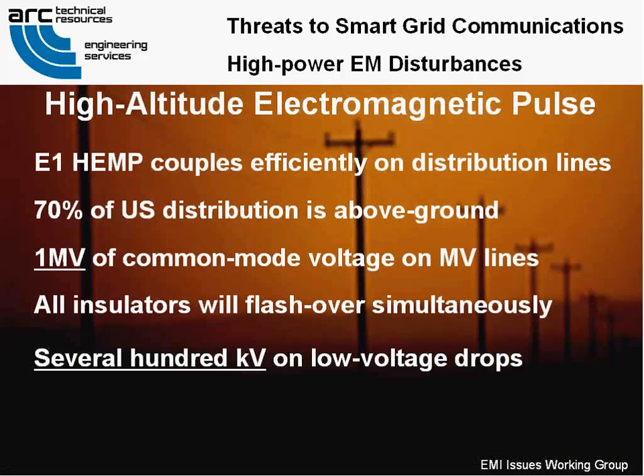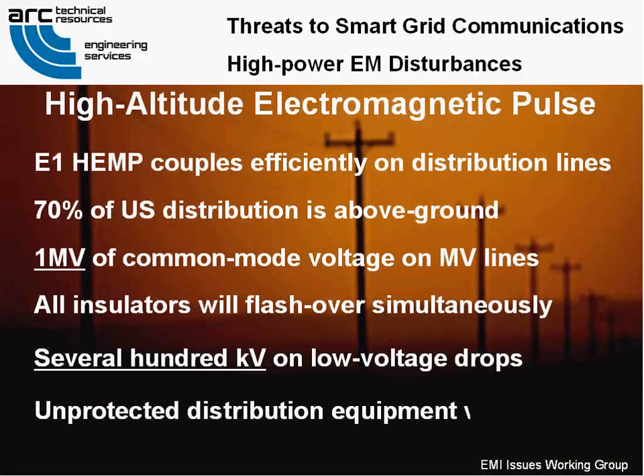Distribution line sensors and controls would be fully exposed to the E1 HEMP, so assets without protection on the sensors, cabling, control electronics, and communications lines will probably be lost. Improved high-frequency grounding, filtering, and surge suppression of those products could help. So much of this is out there, it's not likely it's going to get done.